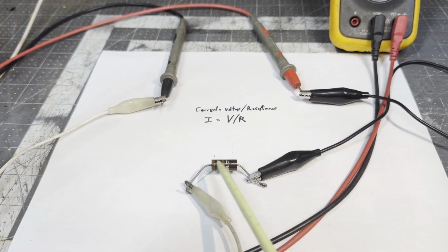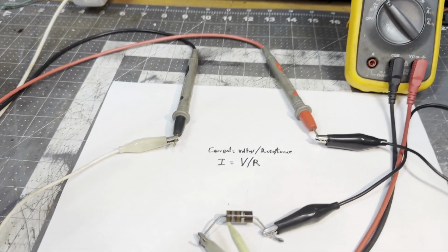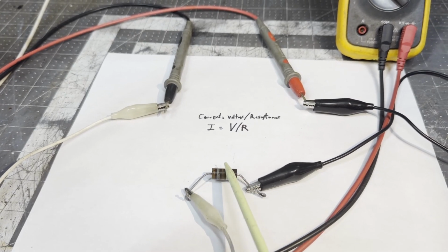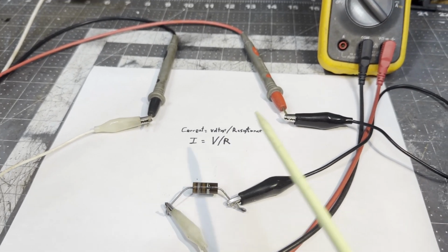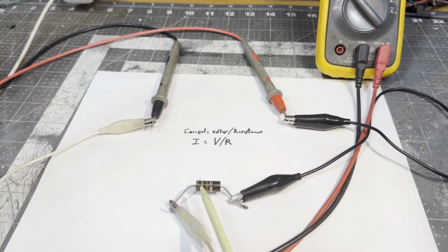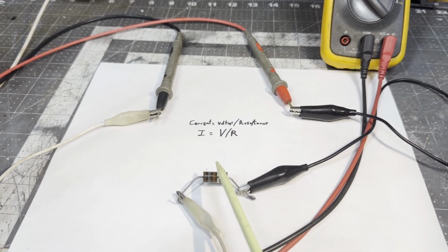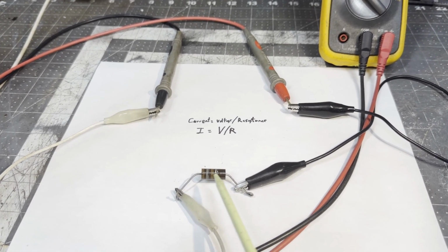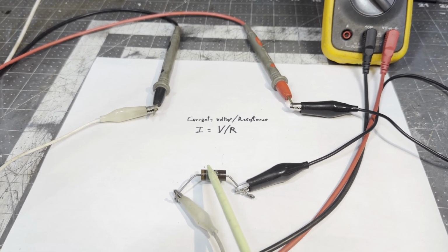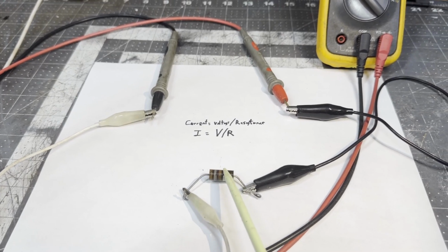So whenever you clamp on either side of a resistor in DC mode, you're picking up the voltage drop. That could be 50, 60, 80 volts — I've seen them drop a lot more or a lot less than that, depending on how much current is going through there. But whatever that voltage drop is, that's what you want.